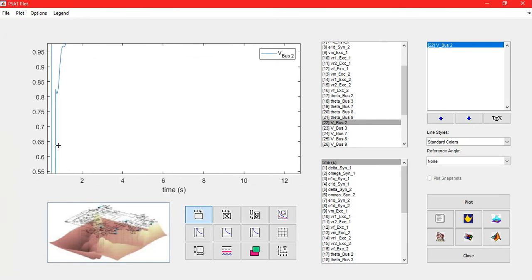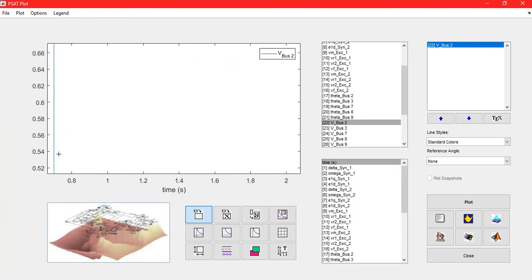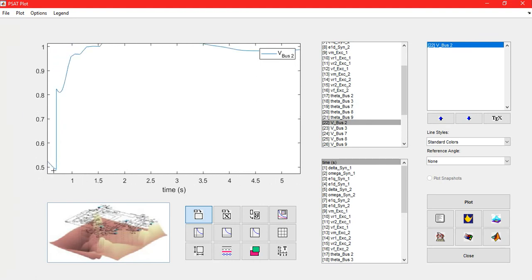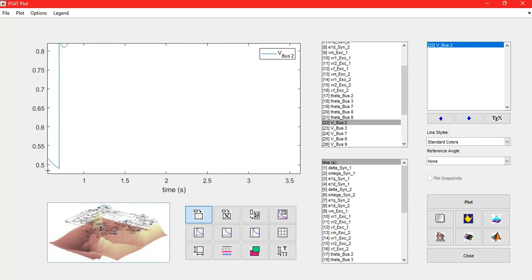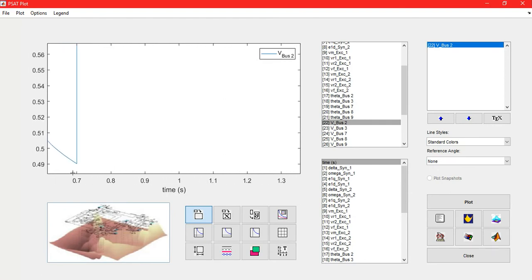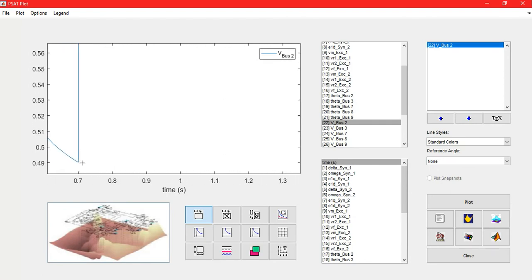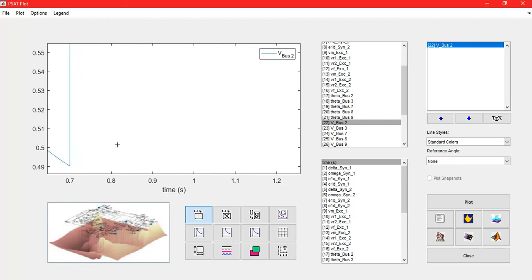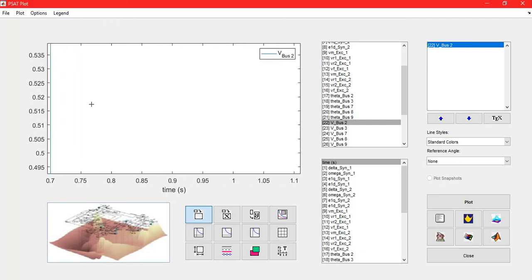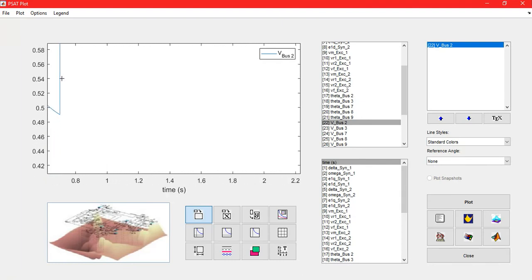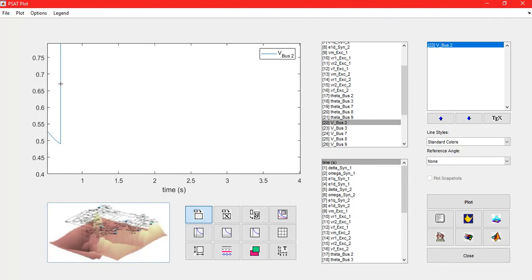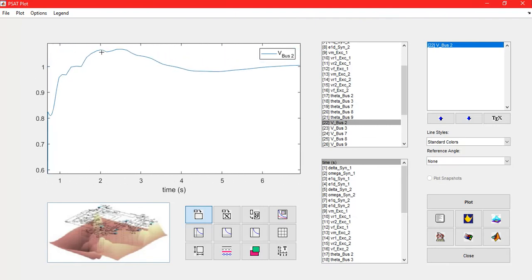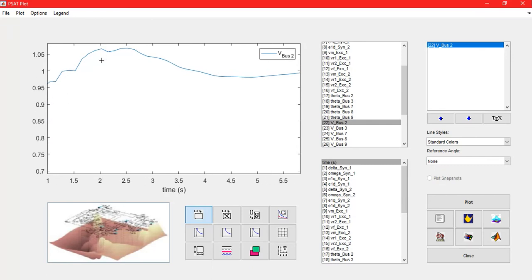Zoom in, you can zoom in how this change is happening here. So you can see at 0.7 seconds the voltage drops very shortly, and just after the clearing of fault it just rises. So you can do all sorts of these plots with respect to any of that.